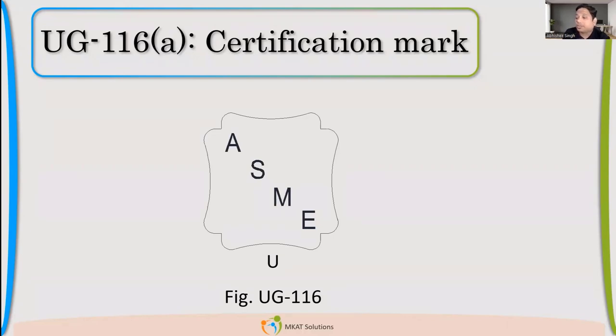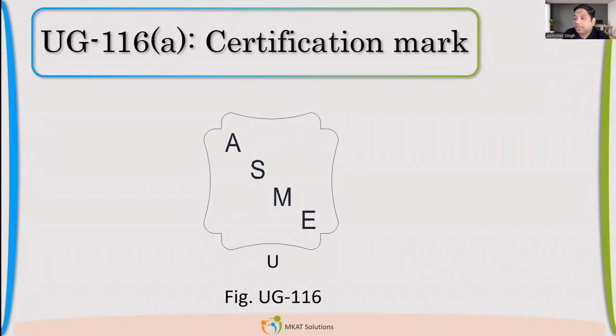Every communication should be in writing. If we follow that, you make the dummy vessel and complete all the process. ASME will come and do the inspection — they will discuss with your designer, marketing, and each and every department. If they are satisfied, they will give the certification mark. It is valid for three years.